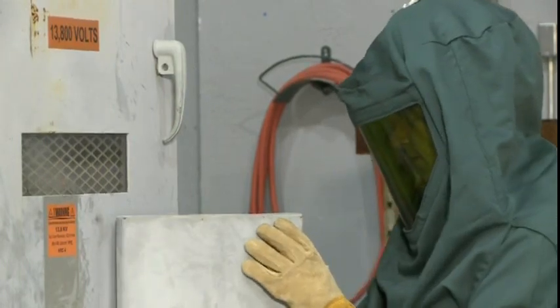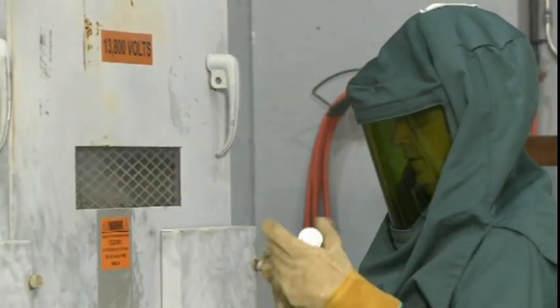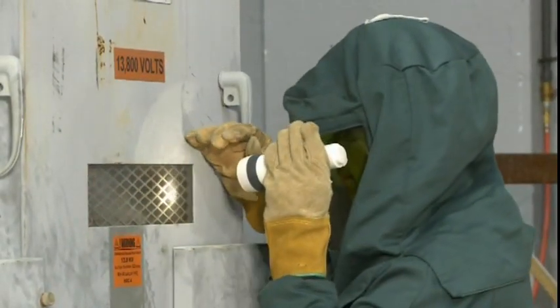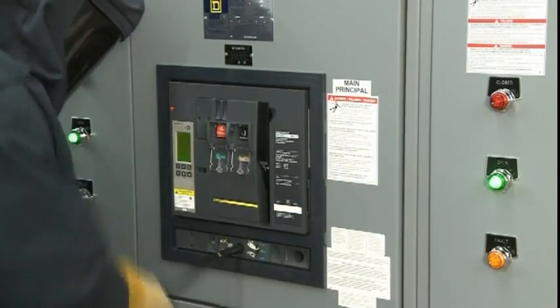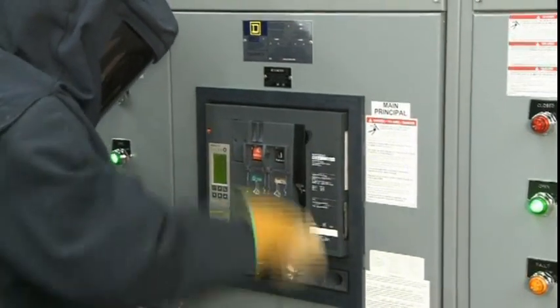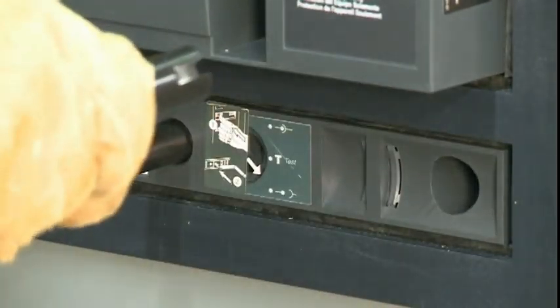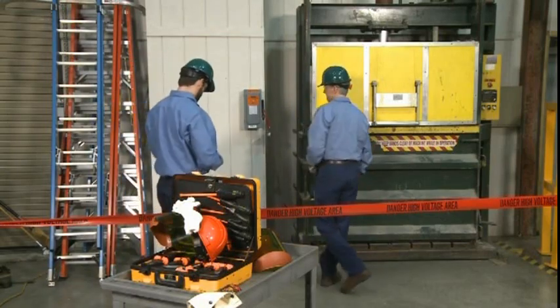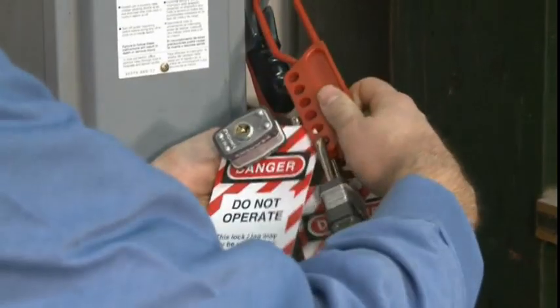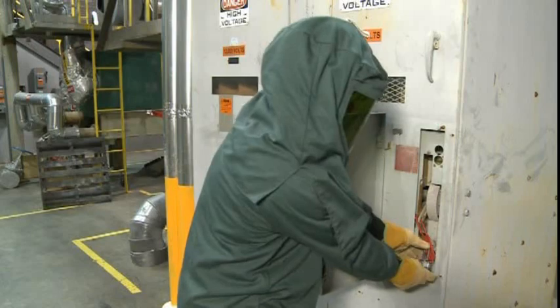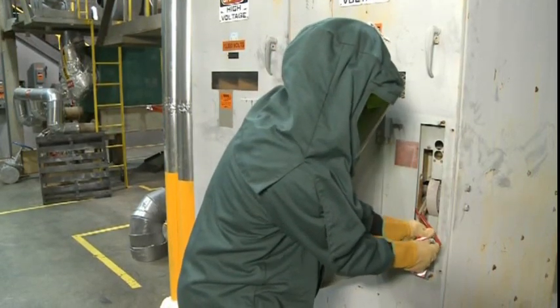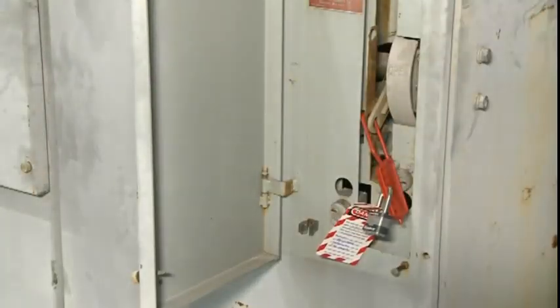Visually verify, if possible, that all blades of disconnecting devices are fully open, or that draw-out type circuit breakers are withdrawn to the fully disconnected position. Then, apply company-approved locks and tags to the open disconnecting devices in accordance with your facility's lockout-tagout procedures. And finally, the most important part: testing to verify that no voltage exists and grounding when necessary.